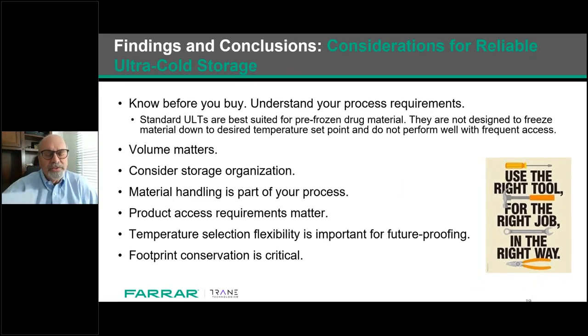Okay, so how do you select the right ultra-low temperature unit? It should start with your process requirements. What's the volume and number of containers that you need to store? And will that material be pre-frozen? Will you need limited access to individual containers, such as a few vials? Or do you need to store and ship bulk containers up to 10 liters? Is temperature flexibility useful and temperature uniformity critical? Do you need to conserve footprint and capital investment by having options on temperature ranges within the same equipment and improved reliability, reducing spares? Next slide.